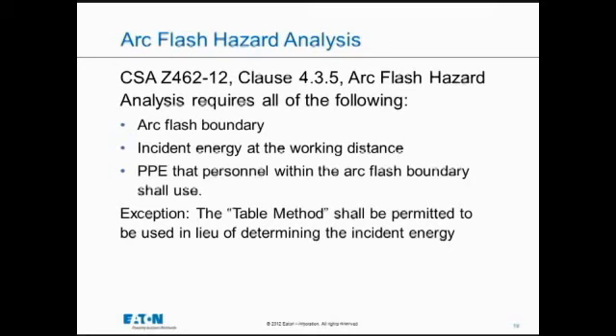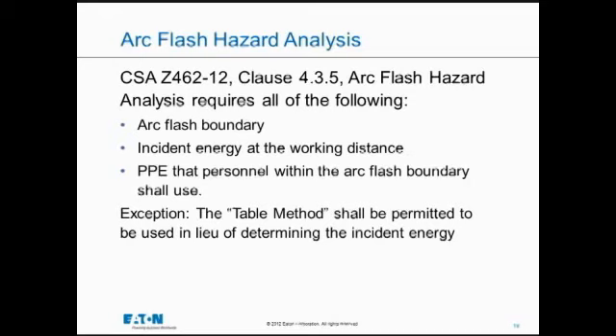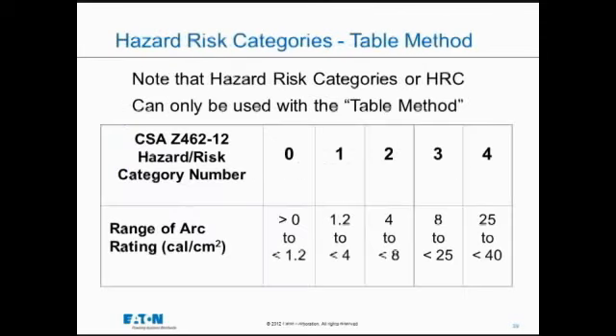Inside the standard, this is the new standard in 2012, there's a requirement to do all of the following: calculate flash boundary, calculate energy coming at the worker's distance, and the worker distance is to face and chest, not to their hands. And then you would figure out your personal protective equipment based on those calculations. The exception to that is using a table, and the table method is permitted to be used in lieu of doing energy analysis calculations. And we get back to, a lot of people are familiar with HRC, hazard risk categories, and those values are still available inside the 2012 best practice guide.